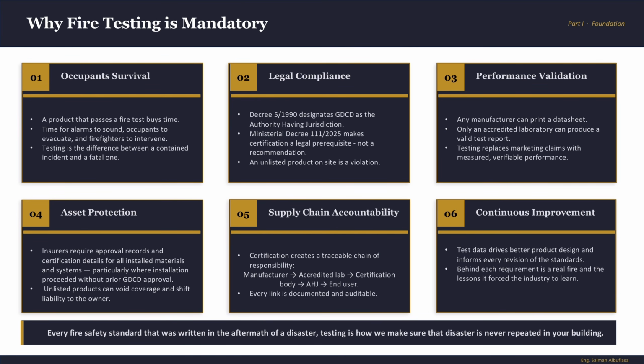It makes a difference. Reason 2, legal compliance. The product certification or product conformity stage is not an optional phase. That is a legal prerequisite to obtaining the NOC or the final safety certificate. So that's not a recommendation, not best practice, and not optional. That's a legal prerequisite requirement. That means any unlisted product found on site is not a technical deficiency. That is a violation, and legal consequences will follow from that.